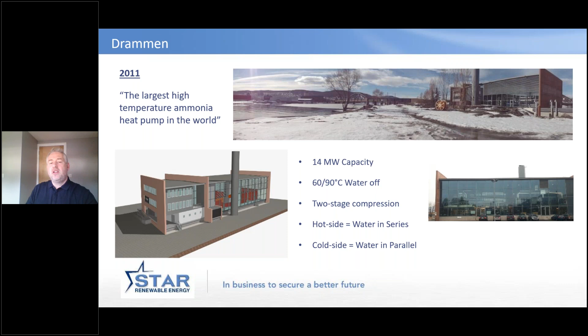We've also got 3 heat pumps in series, so actually it's a 60 to 70 heat pump heating water, and then the water's heated from 70 to 80, and then it's heated from 80 to 90, and that gives us an average efficiency more akin to what we would get if it was only an 80-degree heat pump. So we've tricked the science, if you like, to get 90 degrees out from a heat pump that's got the efficiency of an 80-degree heat pump, and that's absolutely key. Heat pumps are a very honest device. You put electricity in and you get heat out, and the ratio comes down to how good a job you've done.